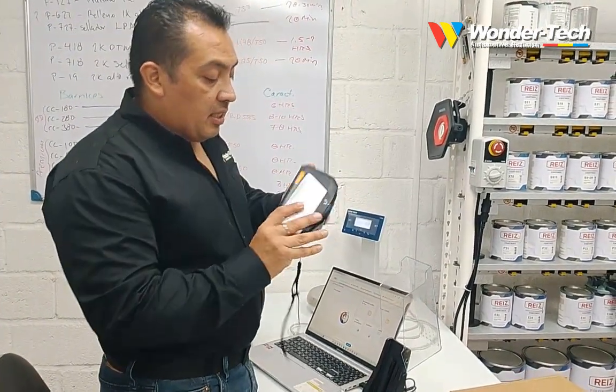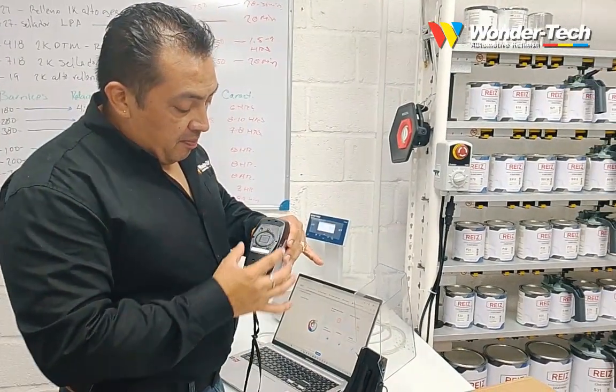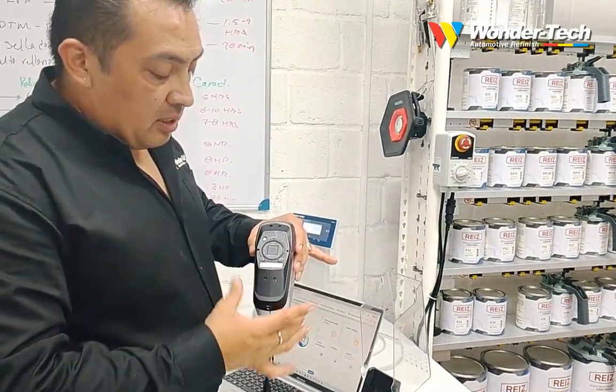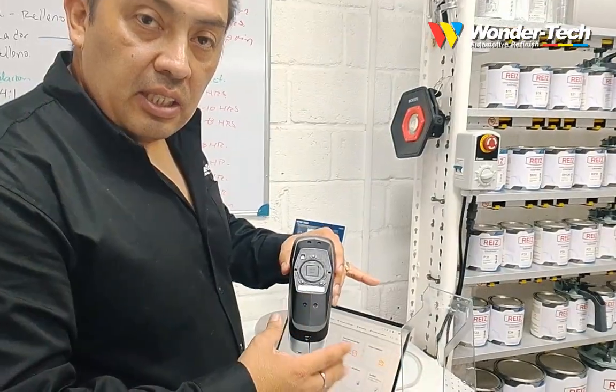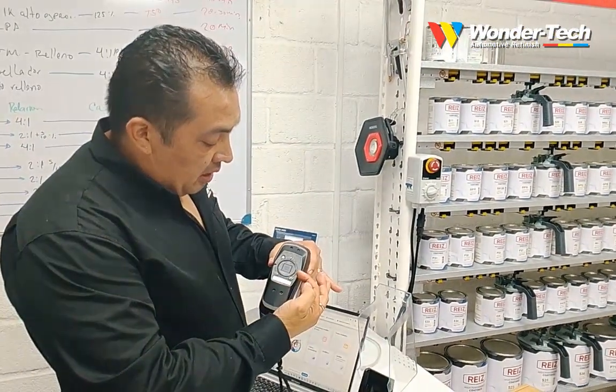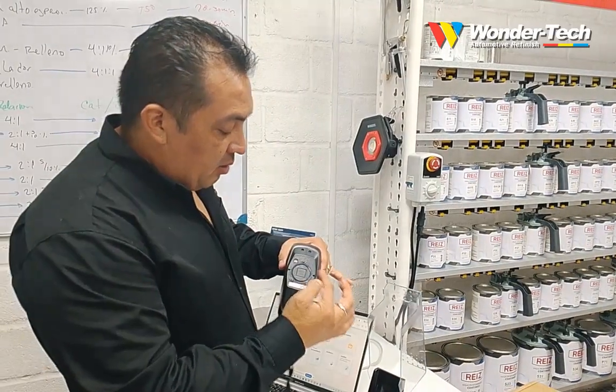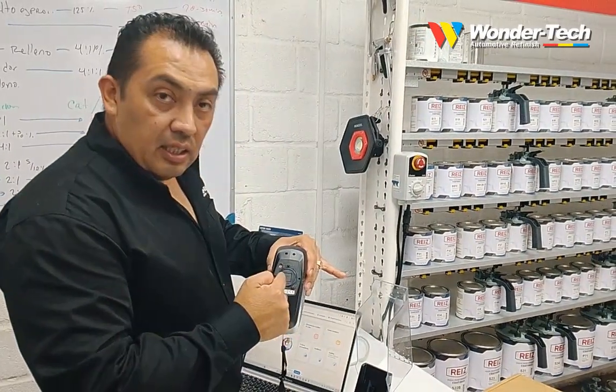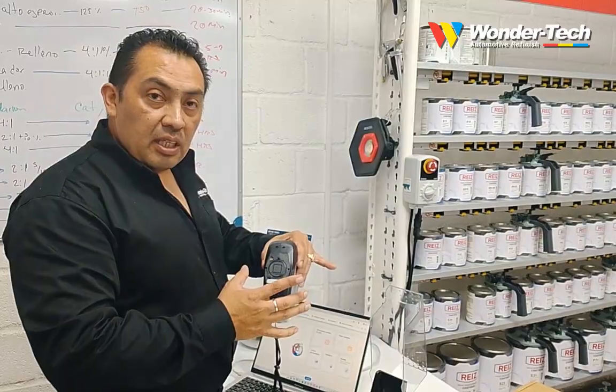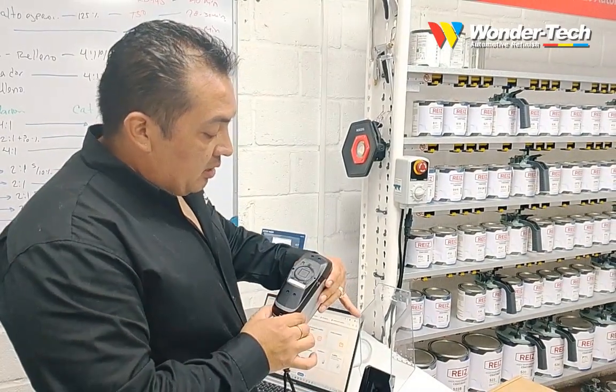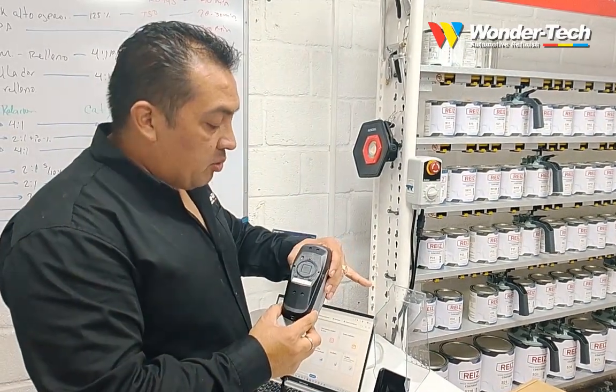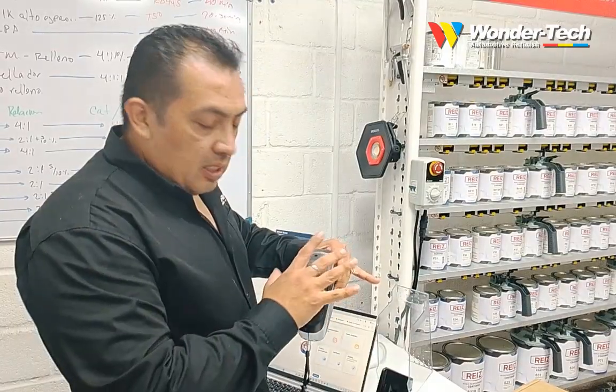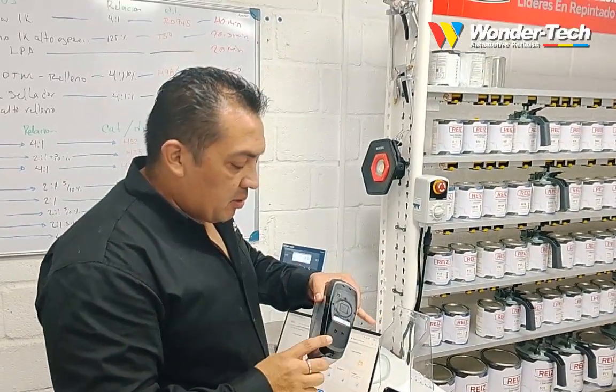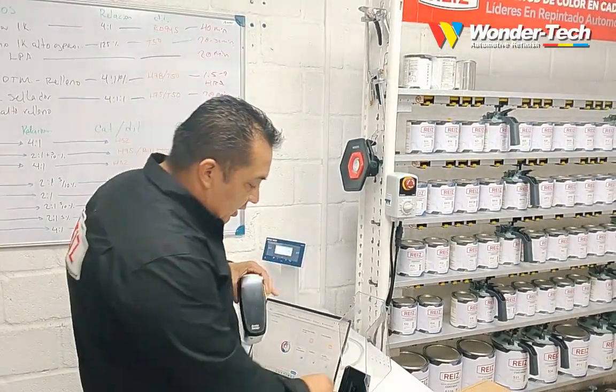On the bottom of the instrument, you'll find the measurement sensors that make direct contact with the color sample during a reading. One thing I'd like to emphasize is that you should never apply pressure to the measurement aperture. As indicated on the device, it clearly states, "Do not push." Please handle this area with great care. Likewise, avoid touching the sensors directly. This is a sensitive area of the instrument and should remain clean and protected at all times to ensure accurate measurements.